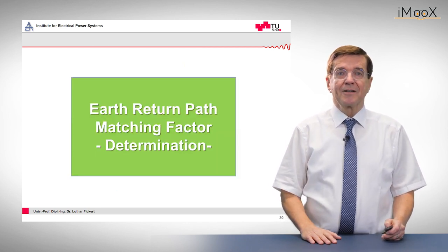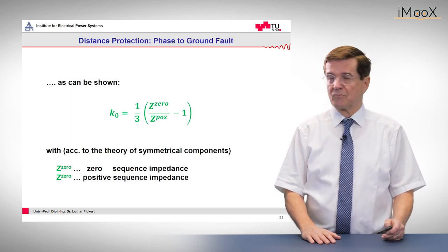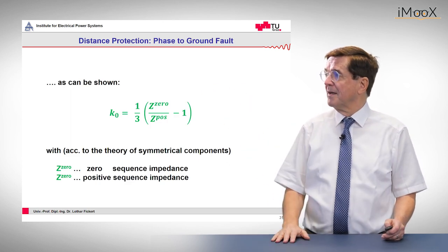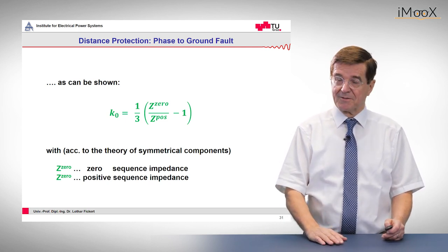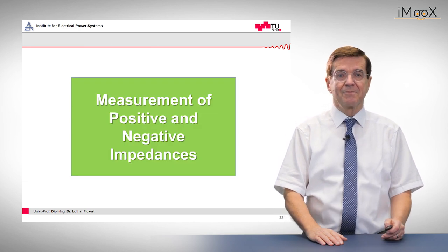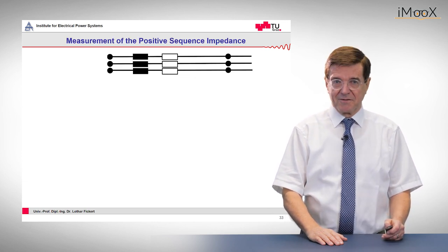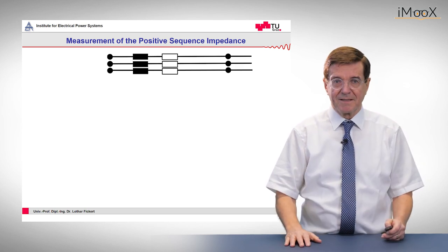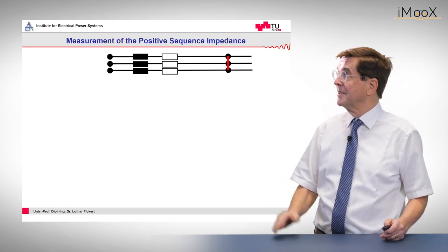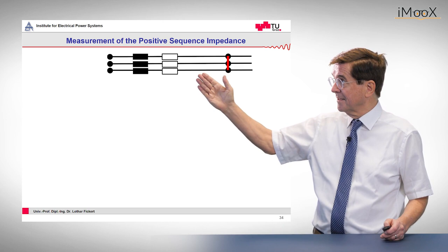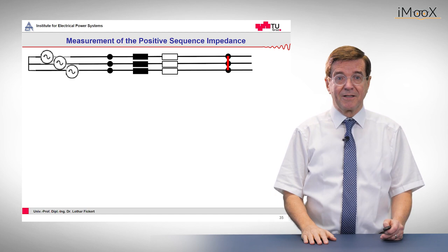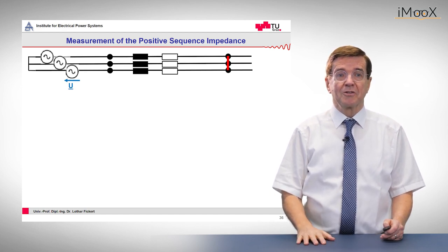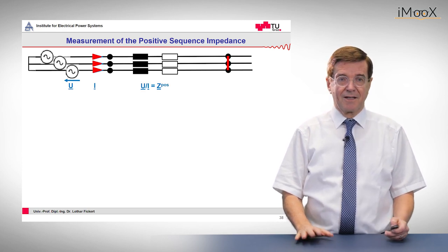So how can this factor be determined? We have seen this formula, and now we need two components: the zero sequence impedance and the positive sequence impedance. The positive sequence impedance is the normal load flow impedance, determined by short-circuiting the line at the end, then applying a symmetrical voltage at the beginning, and determining the quotient between the voltage and the current. This gives the positive sequence line impedance.